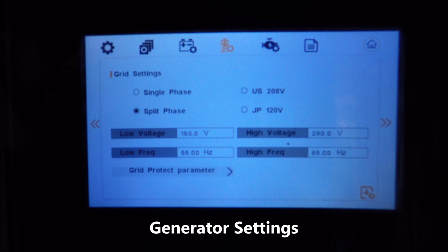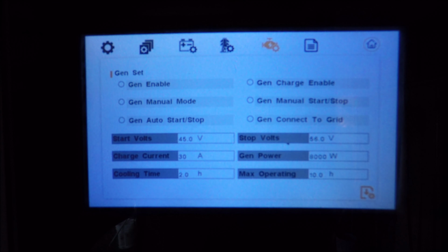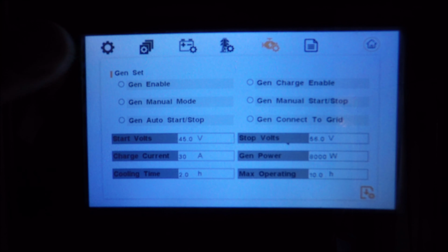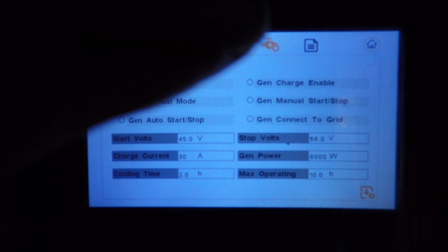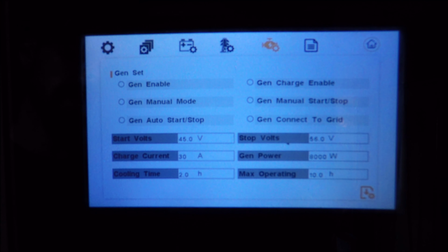Next we'll cover the generator settings. This is where you can enable or disable the AC input labeled generator on the inverter. You can use other AC input types, such as a microinverter, in this AC input with some custom configuration, but for now, we're just going to cover generators. You can enable the generator. Then you can enable generator charge. This will allow, when the generator is started, for it to charge the batteries. You can have two selections, either manual mode or auto start.